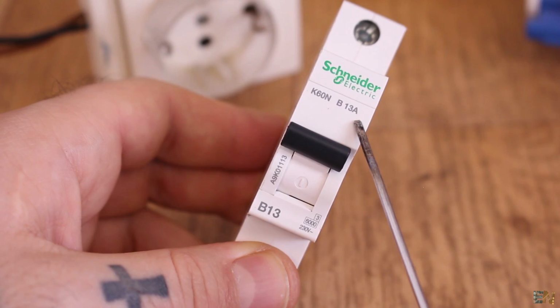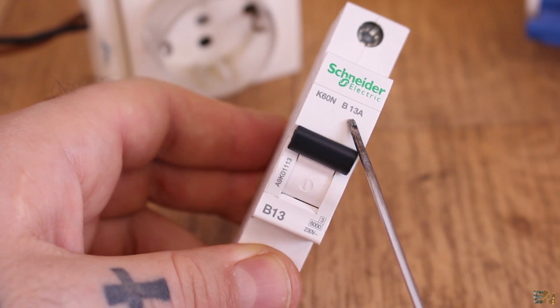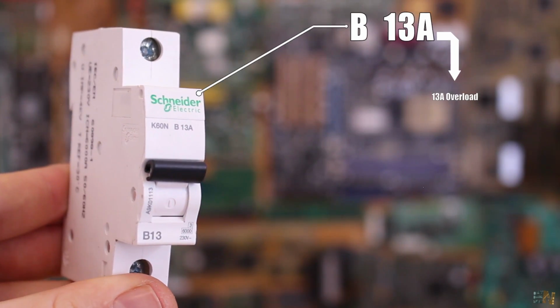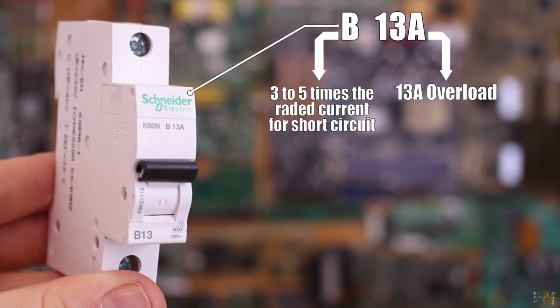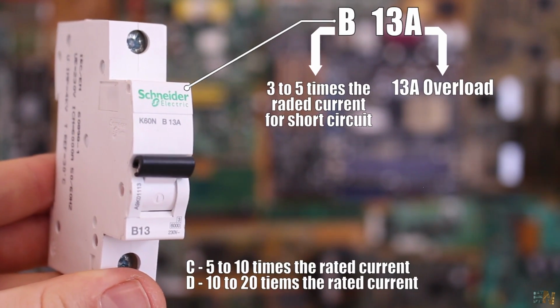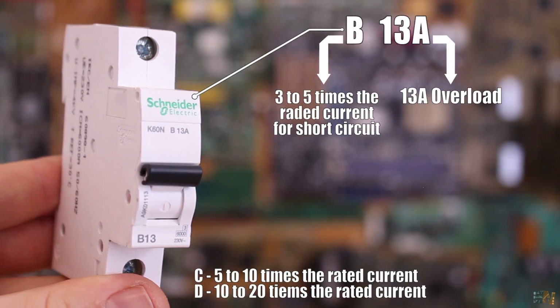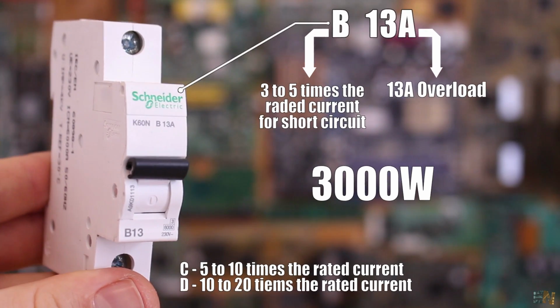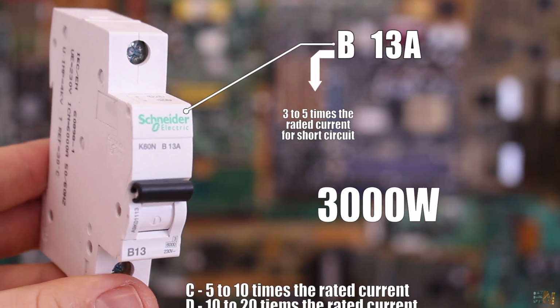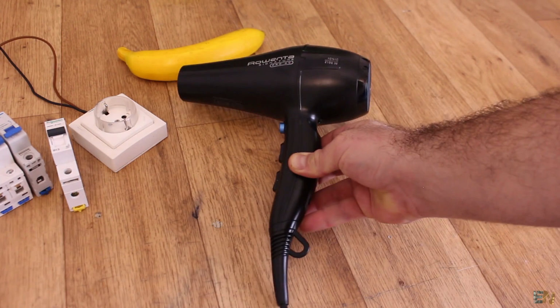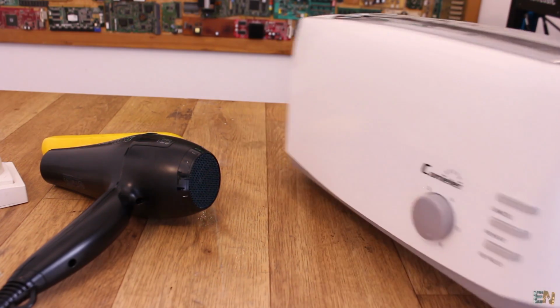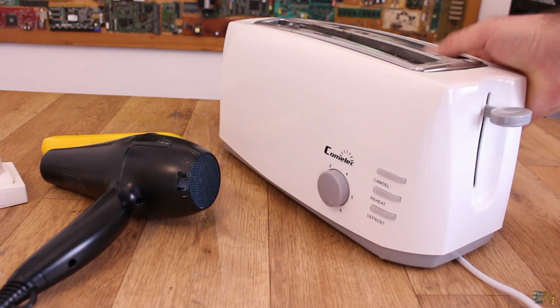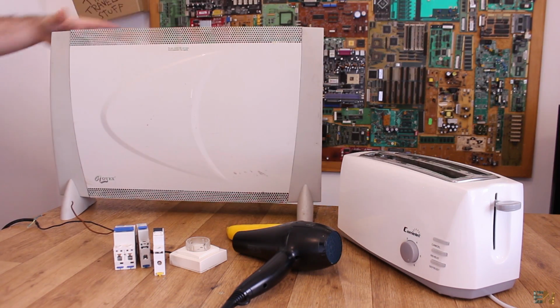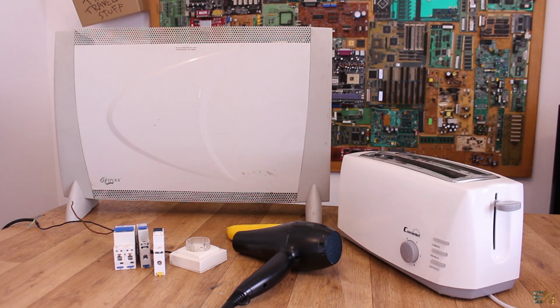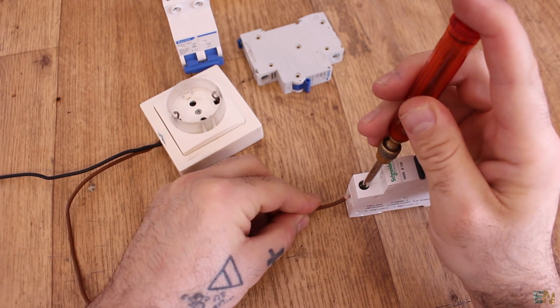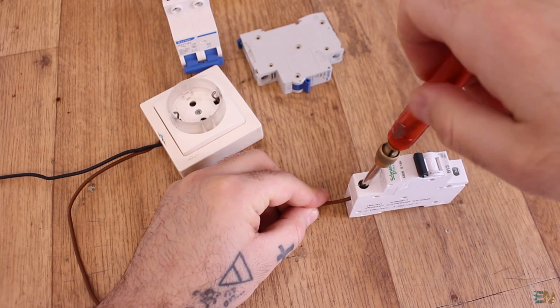This model is a B13, and that means it's rated for 13 amps for a period of approximately 1 hour. 13 amps at 230 volts should be a power of 3000 watts or so. To simulate an overload, I will connect a hairdryer of 2100 watts, a toaster of 1400 watts, and an electric heater of 2000 watts, so a total of 5500 watts, which should be enough to trigger the thermal breaker.